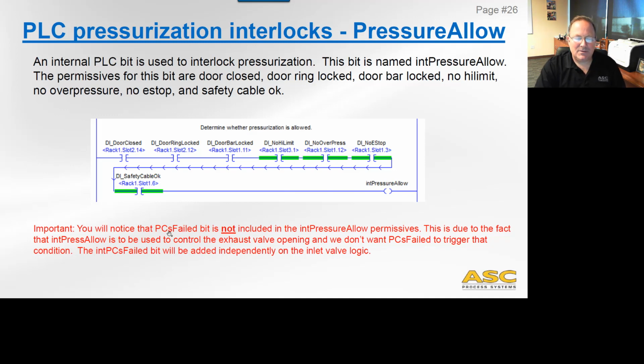You will notice one thing, that the PC failed bit is not in here. So normally we would have interlocks that say, hey, don't allow pressure if the PCs have failed. Well, there's a reason why PC failed is not in this specific coil here. It's not in there as a permissive for this one, because it will be used independently in the logic which uses contacts from this. And that's mainly because we want to use this pressure allow in certain logic that does not use the PC failed signal, okay? If we had a PC fail signal in here, we wouldn't be able to use pressure allow for other logic where we didn't want a PC fail to be there.